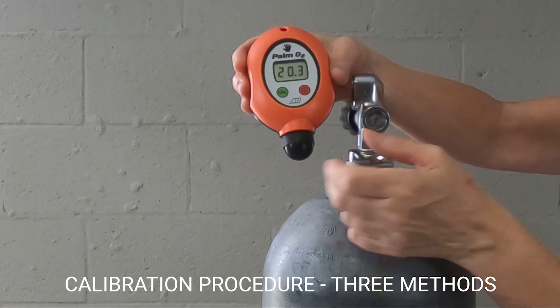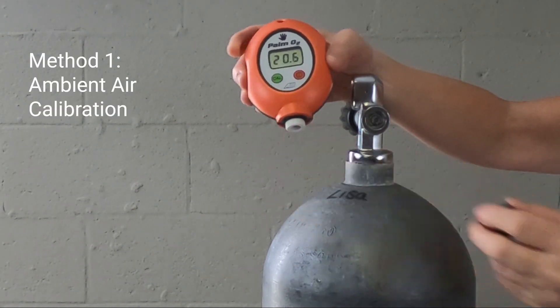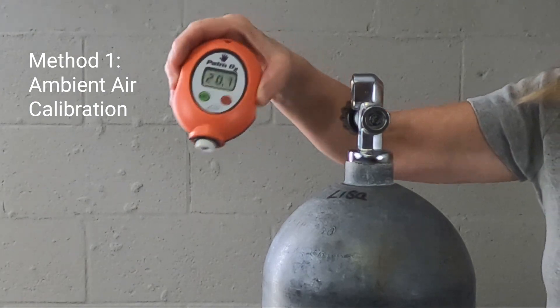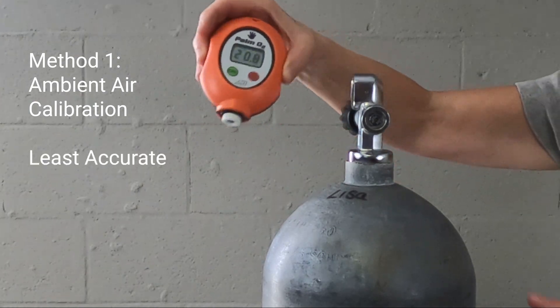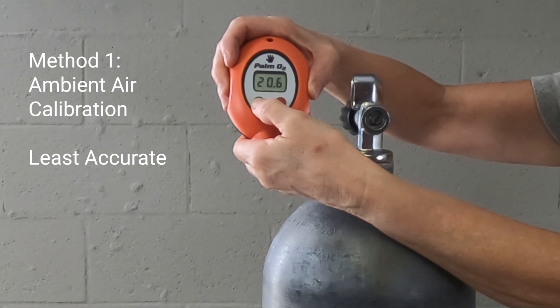The Palm O2 analyzer can be calibrated using one of three methods. The first method is calibrating the Palm O2 with still air. This method is the least accurate since the analyzer is always on a flowing gas.